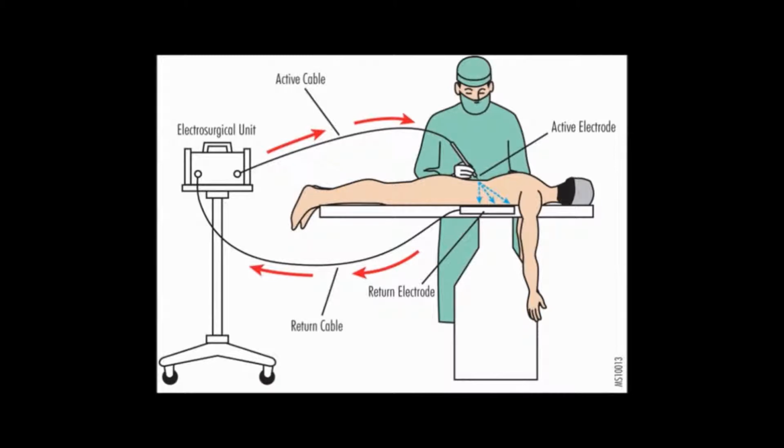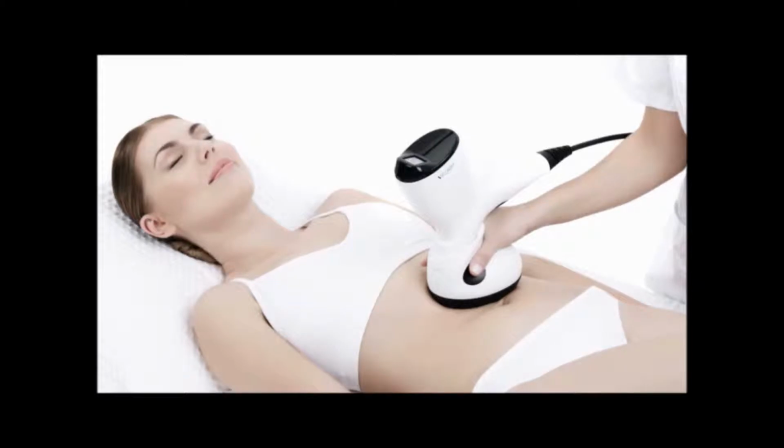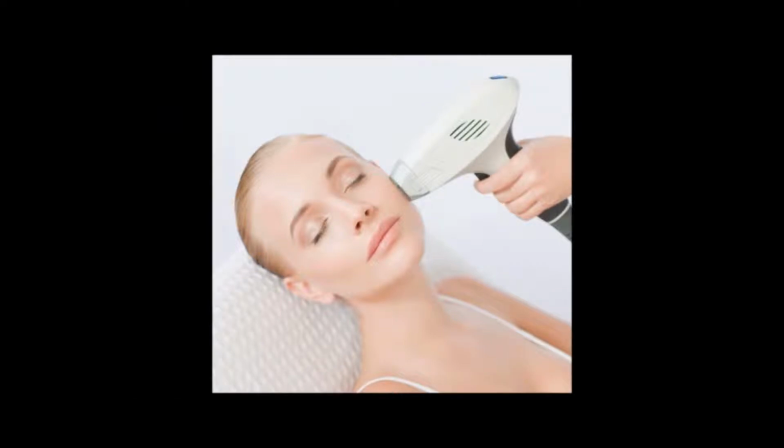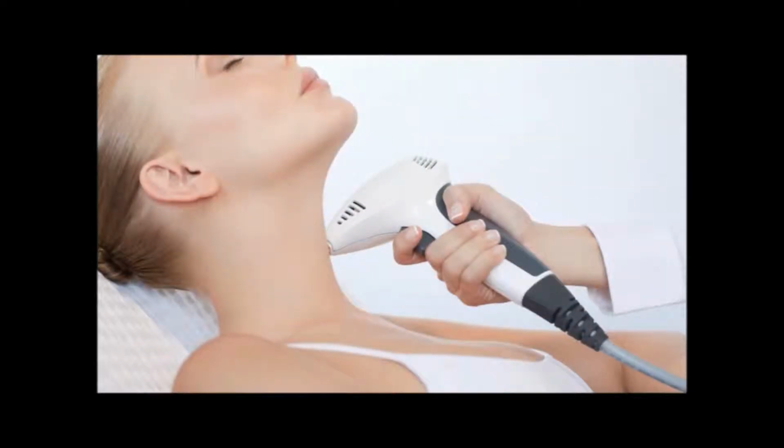RF energy in the form of electrical currents has been used in medical treatments for over 75 years, generally for minimally invasive electrosurgeries, using hemostasis and tissue ablation, including the treatment of sleep apnea. The high efficiency of RF current for tissue heating has also made it useful for electrosurgery and an attractive source of energy for various dermatological aesthetic applications. For medical and aesthetic applications, an RF frequency of up to about 10 MHz is normally used.